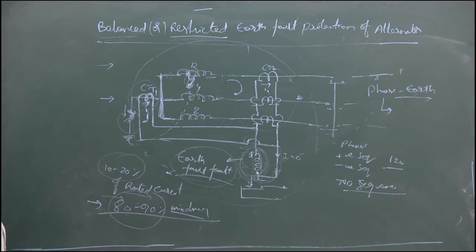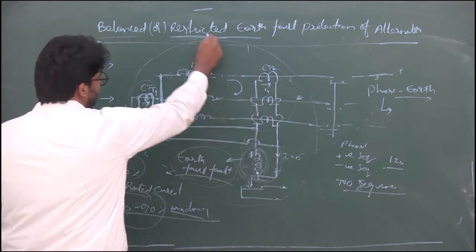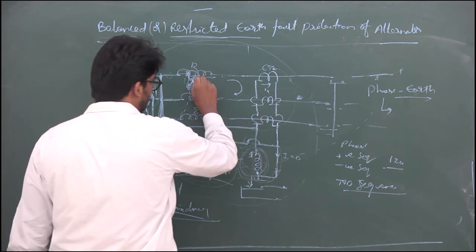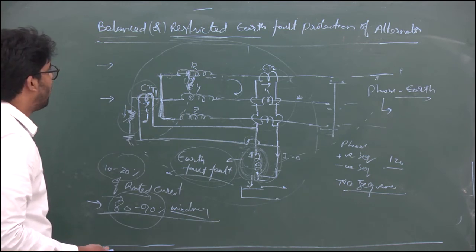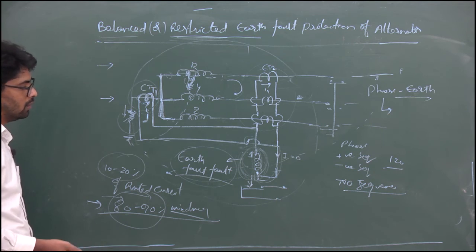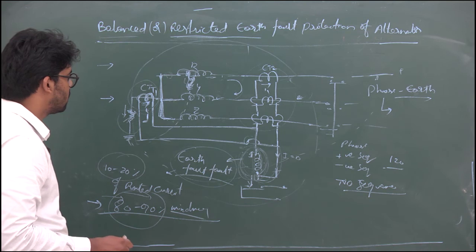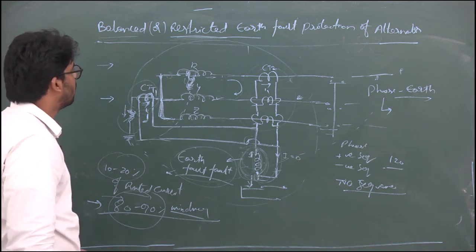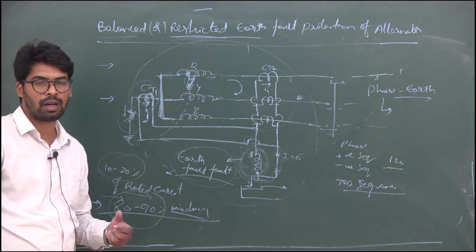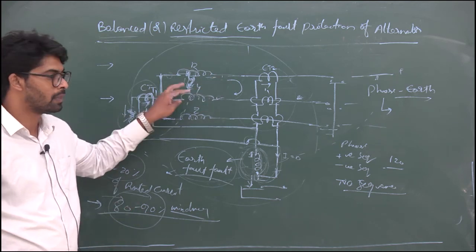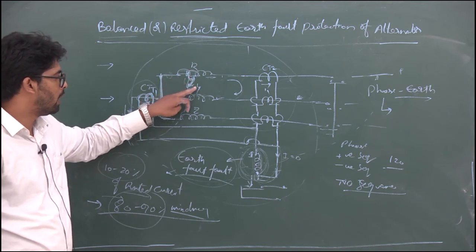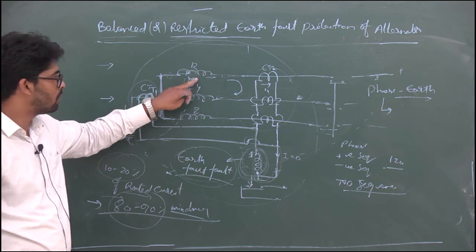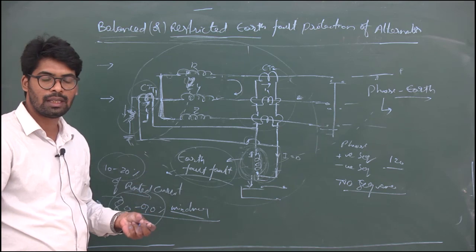This is about the balanced protection. Why we call it a restricted earth fault protection is because this operation — this fault — is only restricted to phase-to-earth fault. It will not operate for any other faults other than phase-to-earth fault, that's why it is named as balanced restricted earth fault protection. This is for small-scale, small generator applications only. In the next class, we will see the inter-turn fault — up to now we have seen faults occurring in the phases, phase-to-earth, phase-to-phase, external and internal, but we have not seen the fault occurring between the windings. We will see that in the next class. Thank you.